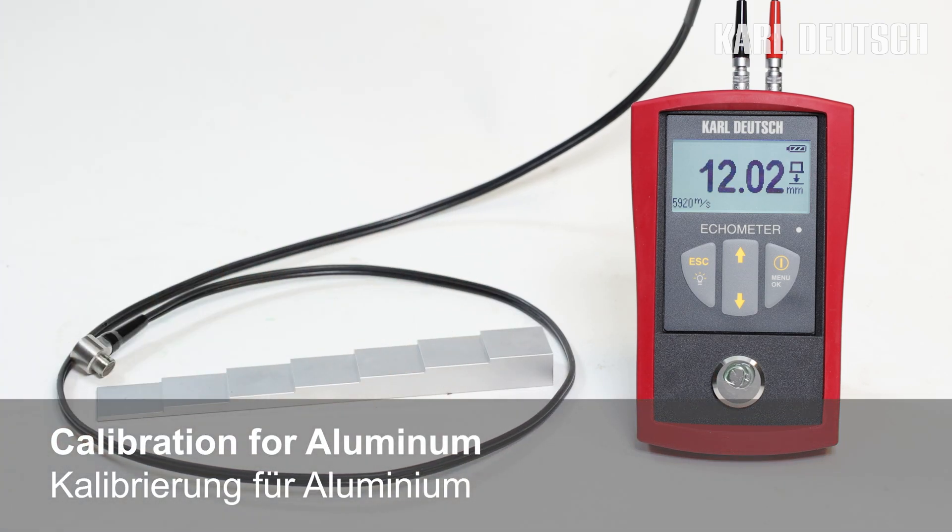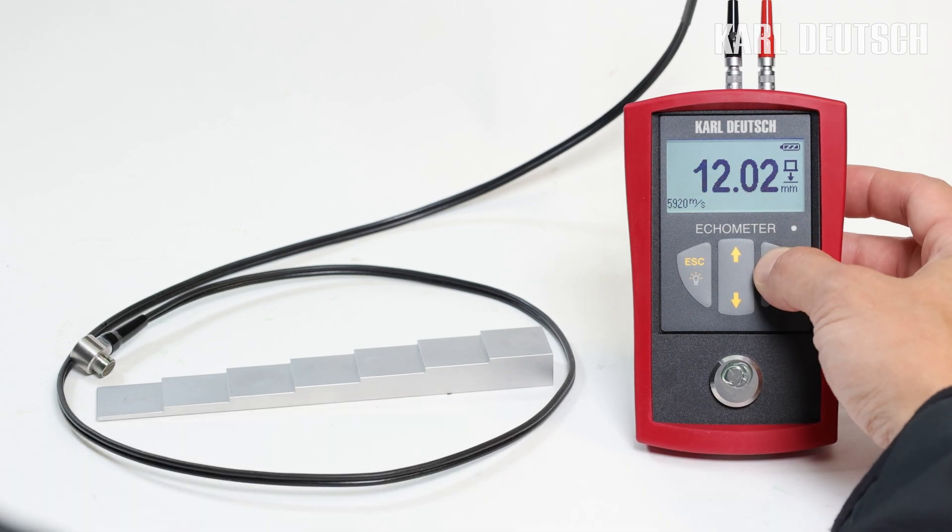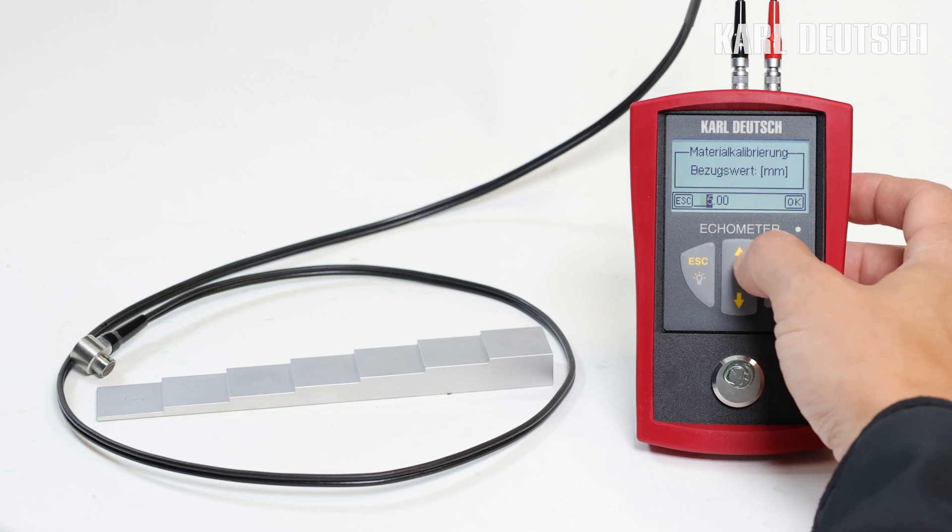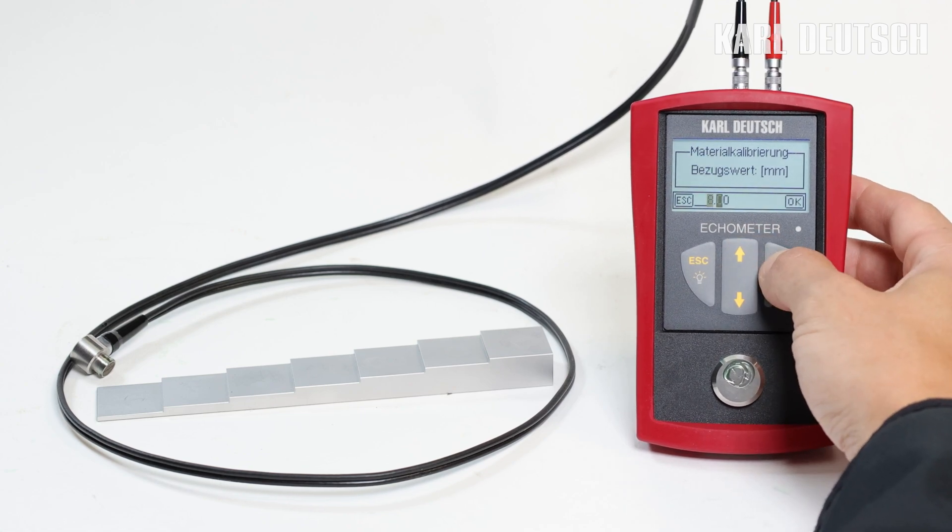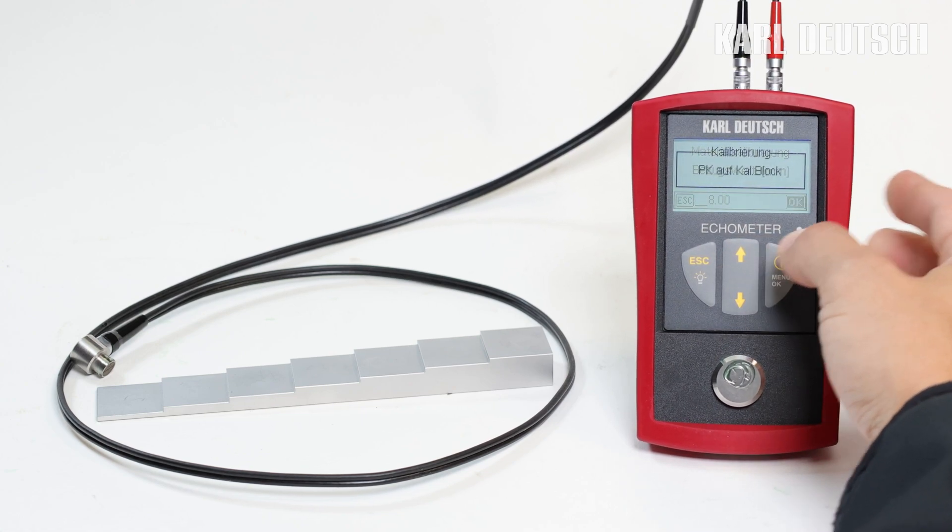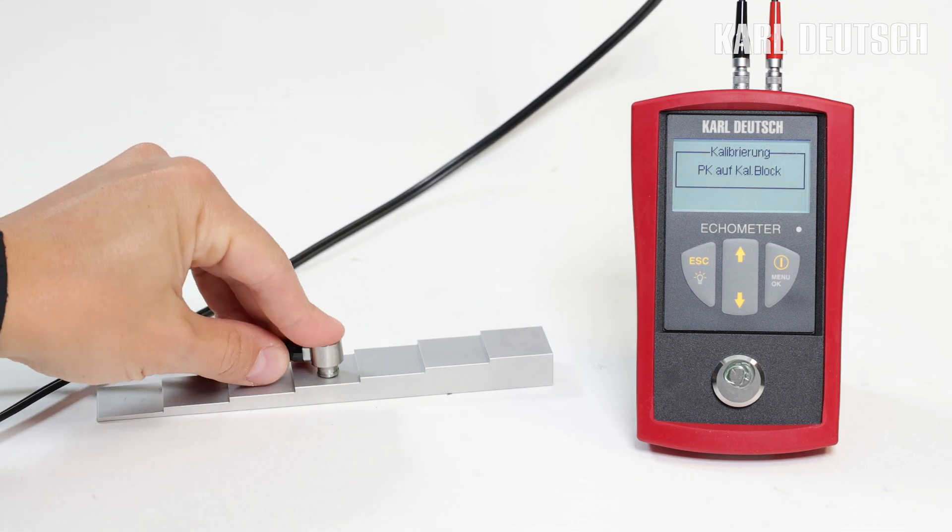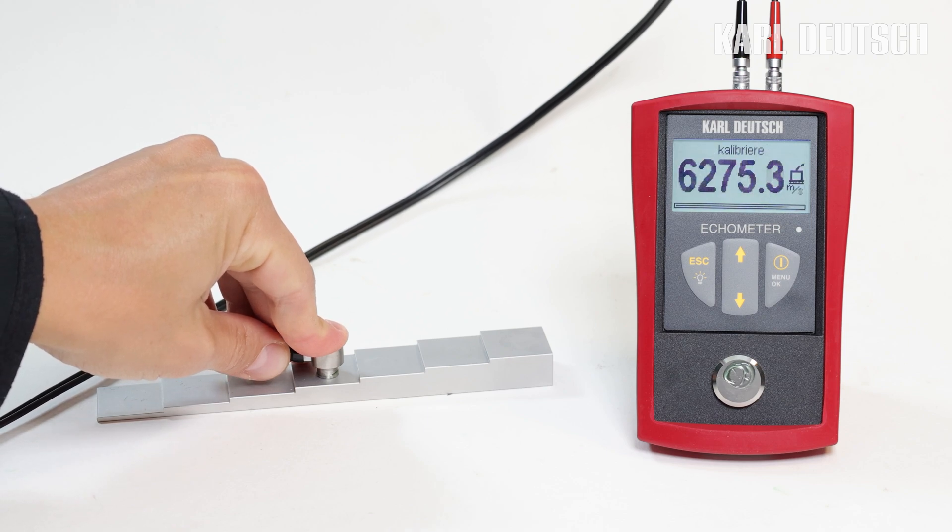How to calibrate the sound velocity I'll show you on an aluminum calibration block. To do this, select the material calibration in the menu and enter the height of the step. Then place the probe with a little coupling agent on the step. The calibration is performed automatically.